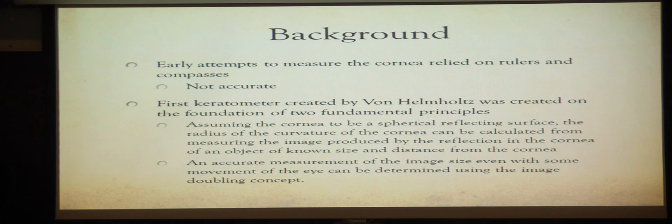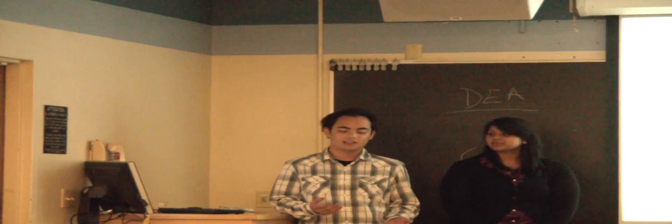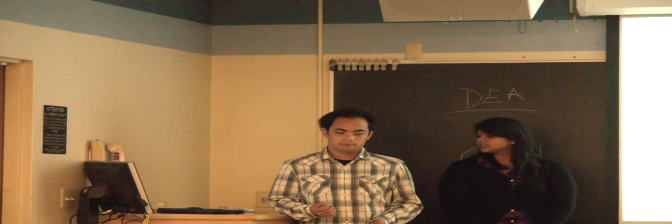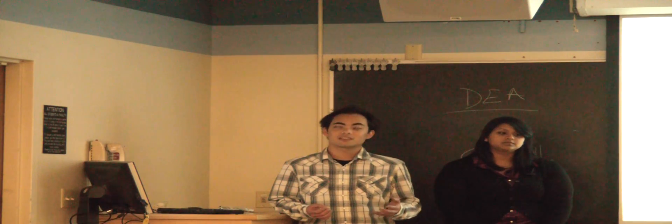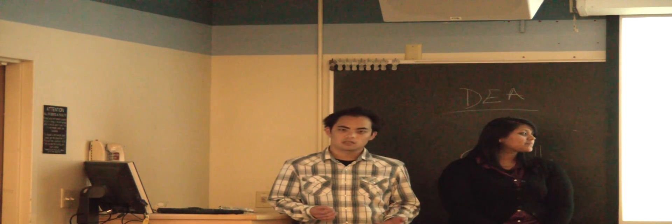The first principle being that the cornea was assumed to be a spherical reflecting surface, and the radius of curvature of the cornea can be calculated by measuring the image produced by the reflection in the cornea, along with the known distance from the cornea. Basically you can treat the cornea as a spherical reflecting surface, and you can easily determine the radius of curvature of the cornea by using laws of reflection and similar triangles.